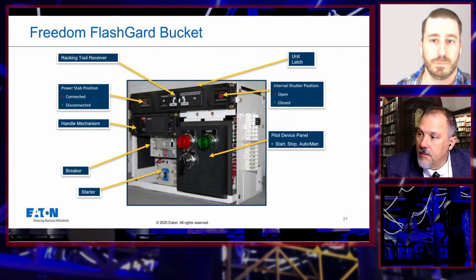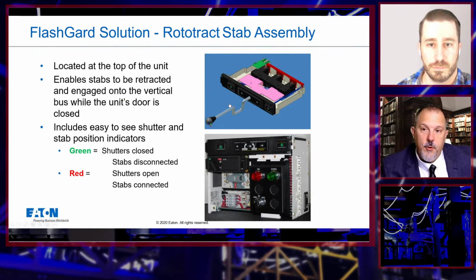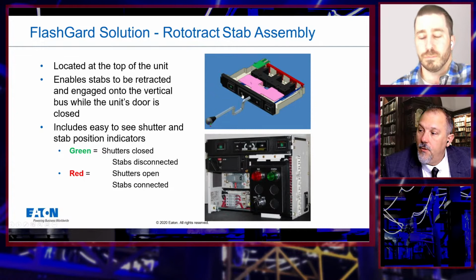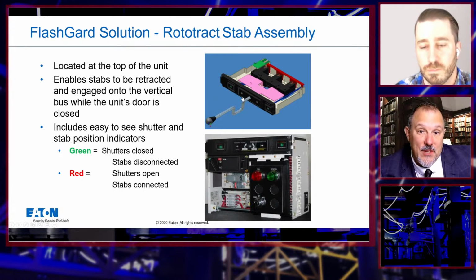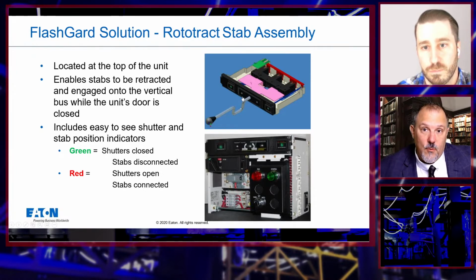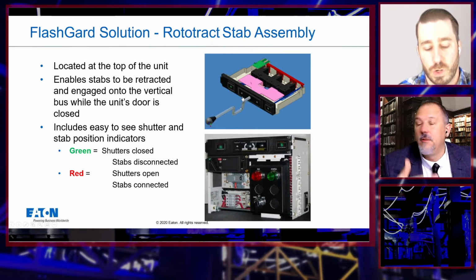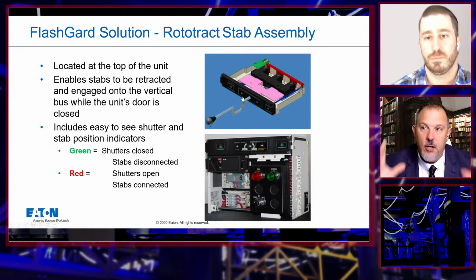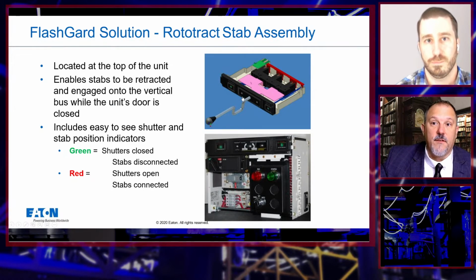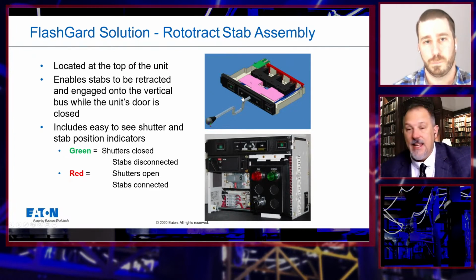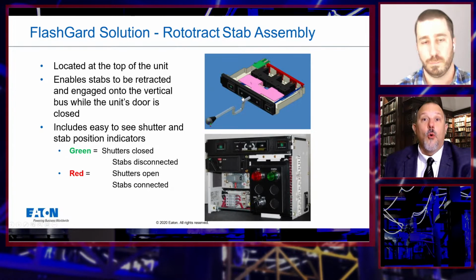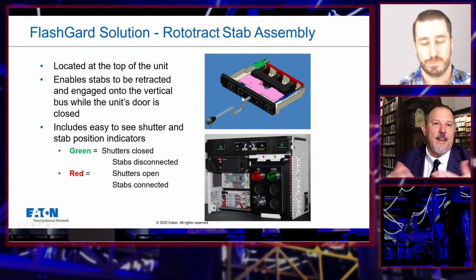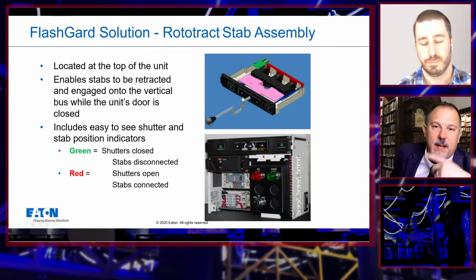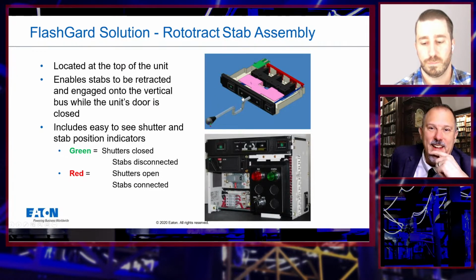So you can take this entire bus via this unit where you have this arm. This is where even this activity - I know we got the doors closed - and we're going to talk about this on Tuesday next week with Russ Seyfried about how we can do things away from the front of the equipment. Even though this is normal operation, I'm racking this off, I've got the doors closed. I probably could put a motorization piece on the front of this and get myself out of the way, and then I'm taking that MCC bucket off of the bus, or putting it on the bus, adding that additional layer of the onion - I'm still going to be away from it even though I have arc resistant equipment. I just don't want to be in front of it.